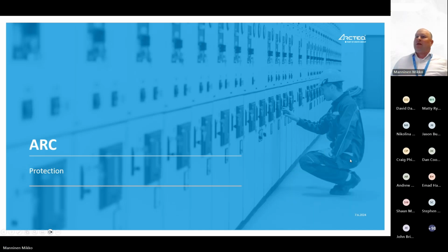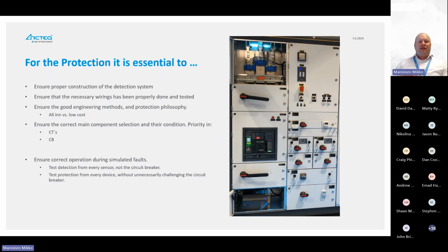Then protection. What is different in detection and protection? For the protection, it is essential first to ensure proper construction of the detection system. And for the detection, you need light, current, or light only, maybe pressure. But it has to be built properly. It has to be designed properly. So you detect the possible arc flash from each and every place inside the panel.